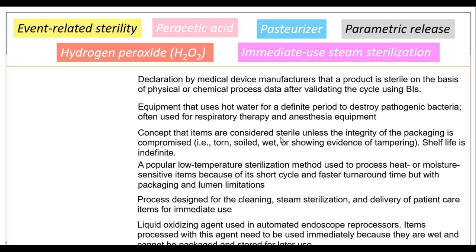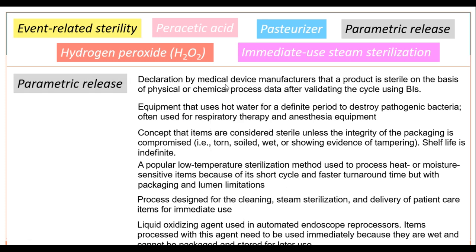Declaration by a medical device manufacturer that a product is sterile on the basis of physical or chemical process data after validating the cycle using biological indicators — that's going to be our parametric release. Very good for those of you who got that.